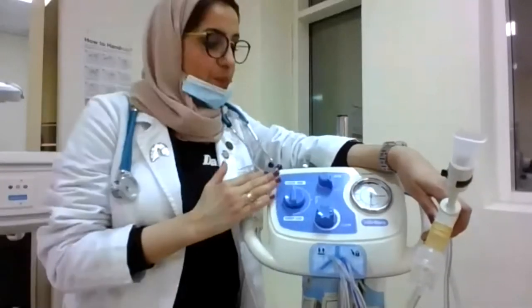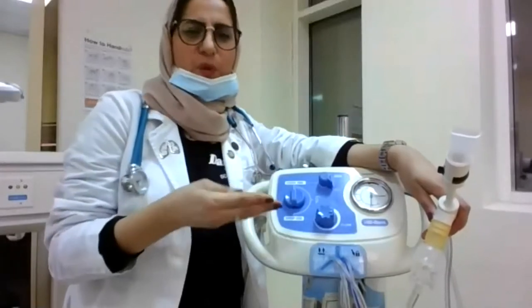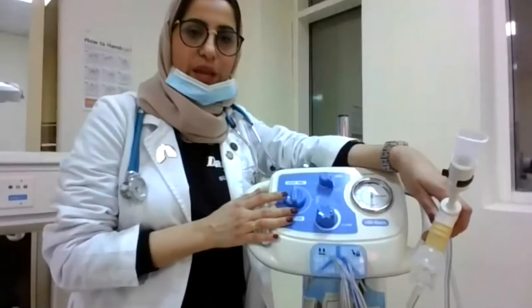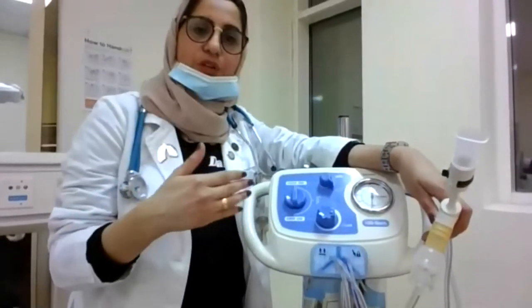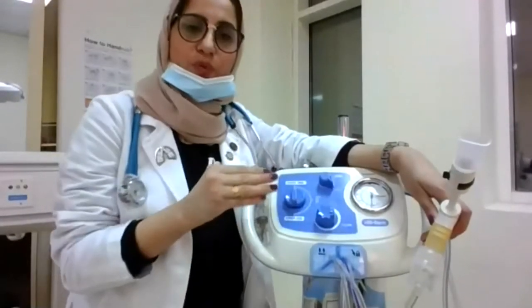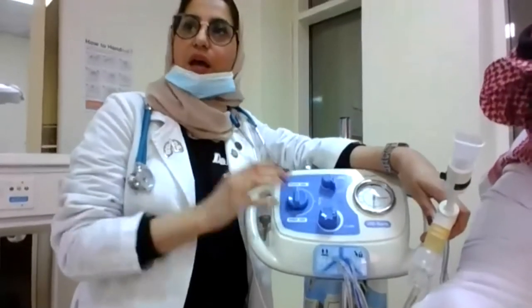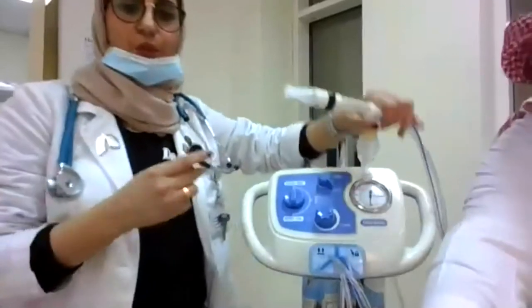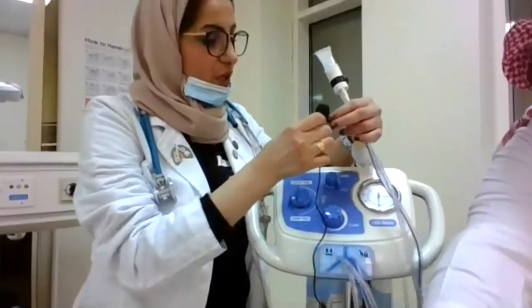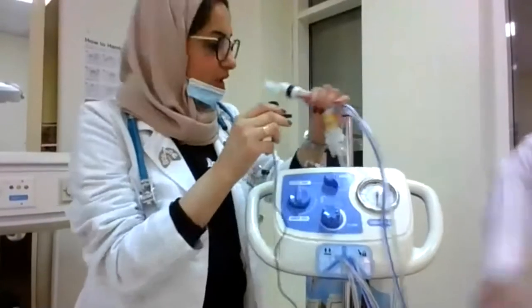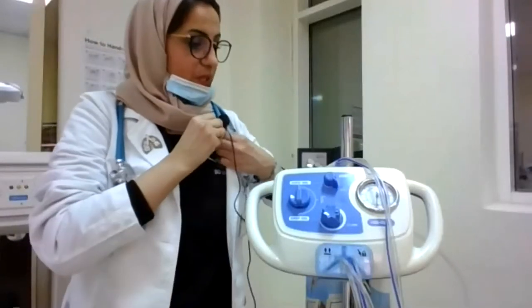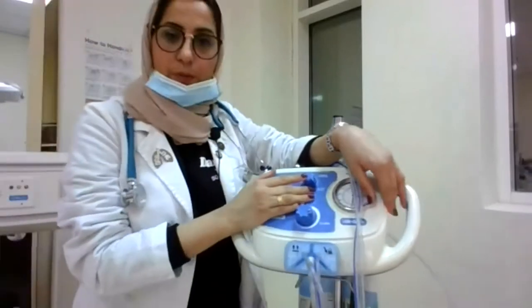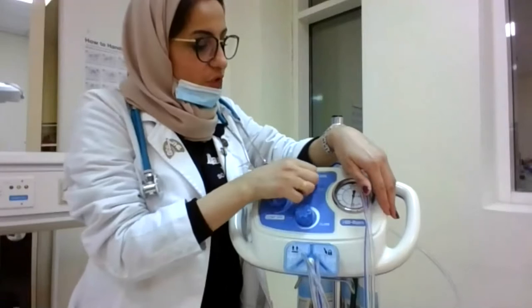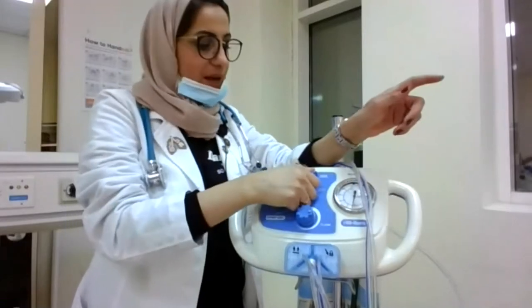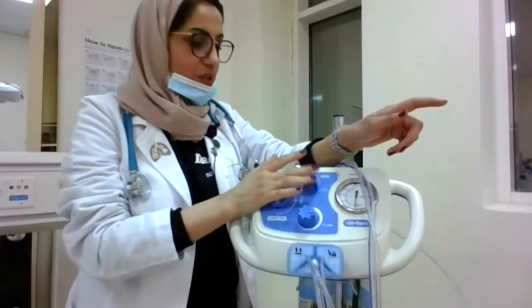During this mode, a pressure gradient will be formed in the lower airway, where the secretion is trapped, and it will help move the secretion from the lower airway to the upper airway, where we could clear the secretion up, or the patient could cough it up. The frequency of the oscillation could be as high as 230 beats per minute, or as low as 170 beats per minute. We could change the frequency of this oscillation through this knob, as high as 230 and as low as 170.